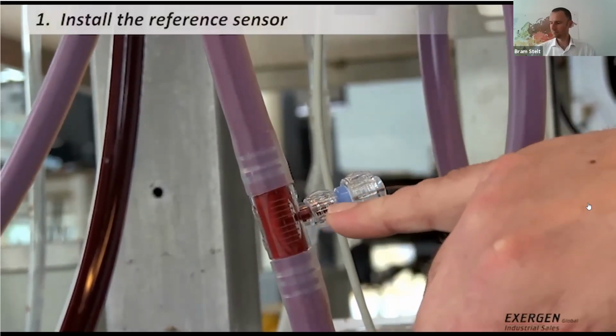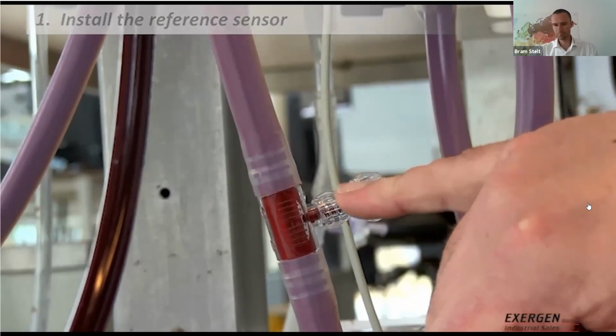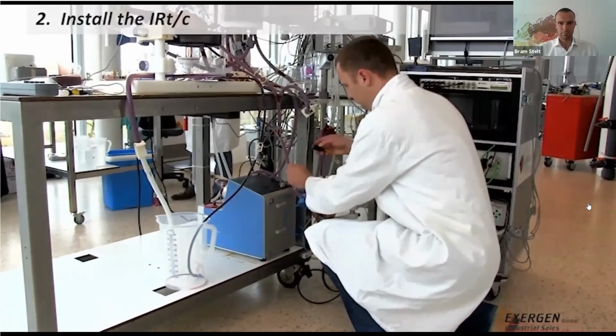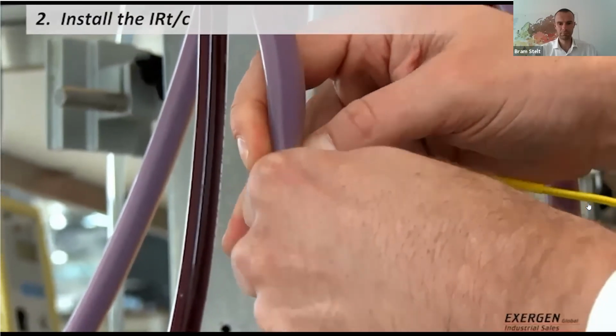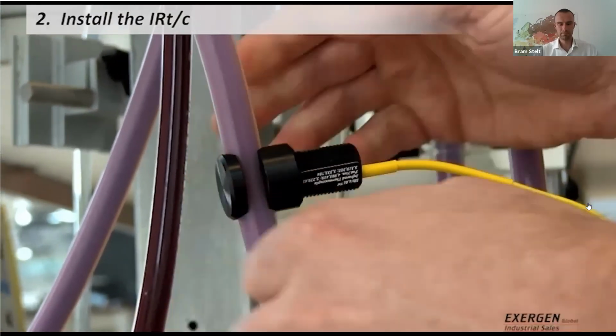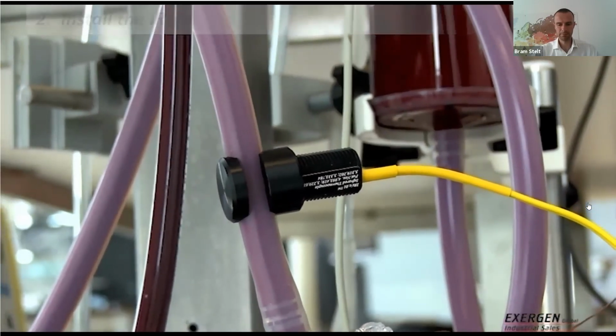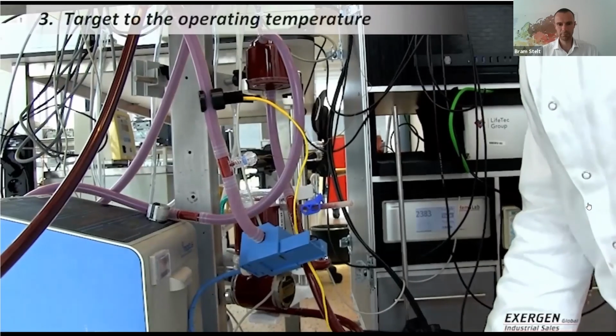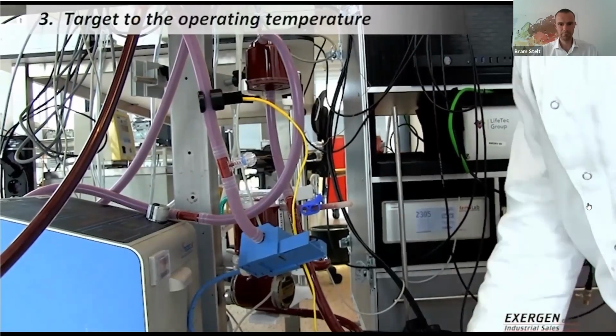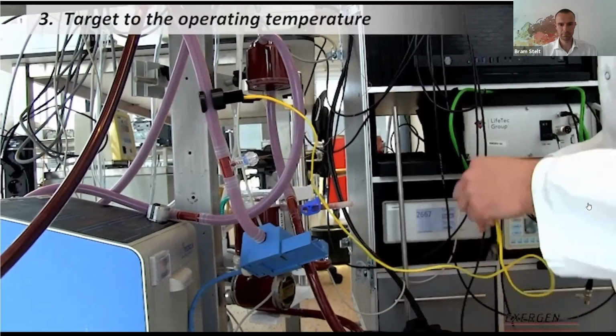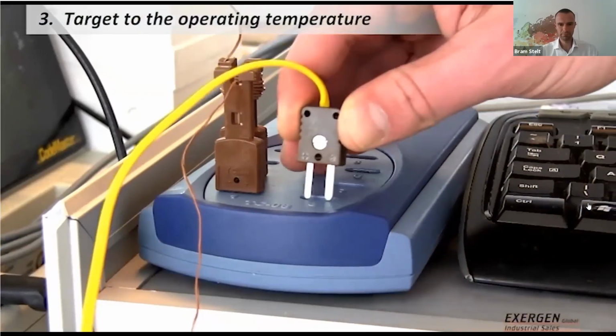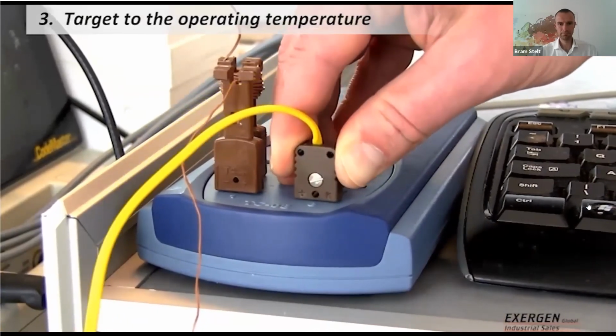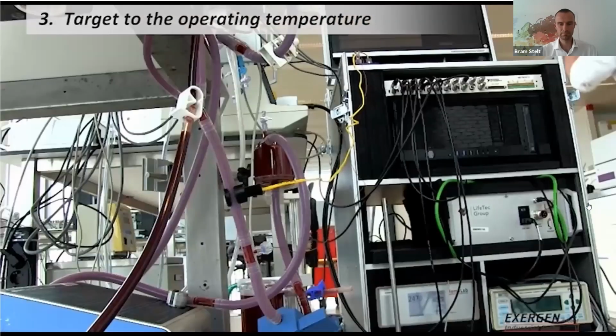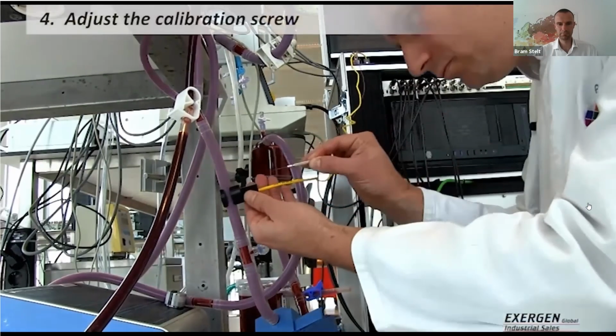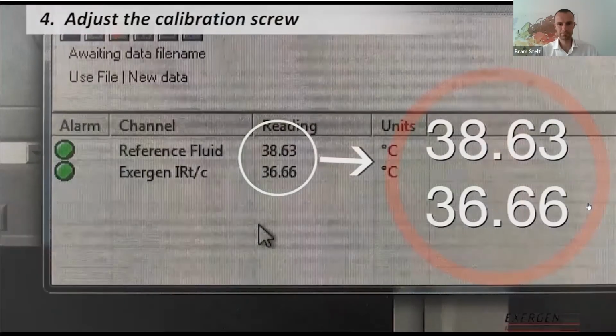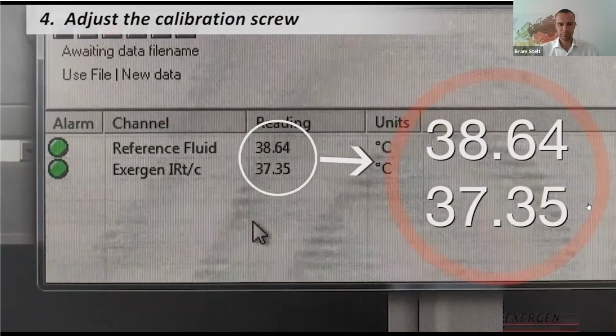Step 1. Install the reference sensor in the fluid. Step 2. Install the IRTC and align to view the desired target. In this case, our convenient mounting clip is used to mount the IRTC on the tube. Step 3. Bring the target to operating temperature, in this case 38 degrees Celsius, as indicated by the reference sensor. Allow the sensor and the clip to reach steady state temperature for approximately 10 minutes. Step 4. Adjust the calibration screw until the IRTC reading matches the reference fluid reading.